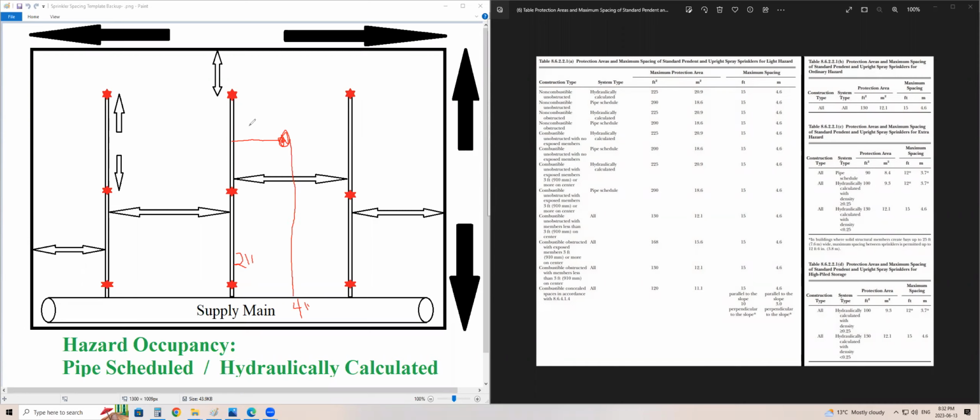That's what everyone ends up asking, because this way, I only need 2 feet of pipe, right? A 2-foot break arm. Whereas coming off the main, this is 60 feet of 1-inch, right? And no guy wants to go and drill a 4x1 mech T and run 6 lengths of 1-inch all the way over here to do that. But the question is, which one's better? What's allowed? Am I allowed to come off the branch line, or should I go back off the main?